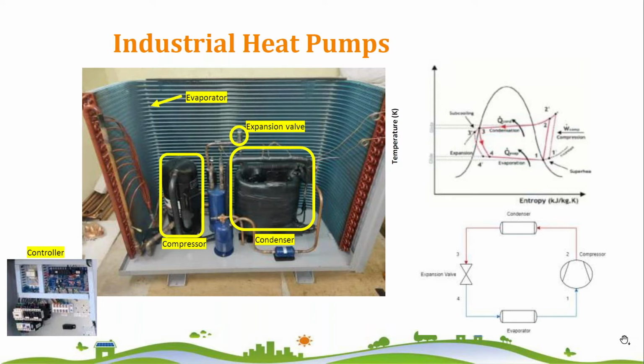Let's get into the working principle of the heat pump. There are 4 main components in the heat pump system: compressor, condenser, evaporator, and expansion valve. Initially, low boiling refrigerant inside the evaporator takes heat from the ambient air or the waste heat from industrial processes and gets boiled. This superheated vapor goes to the compressor where it is converted to high pressure and high temperature superheated vapor, which is then fed into the condenser, where the refrigerant condenses to a subcooled liquid by giving off heat to the process fluid going through the heat exchanger. This subcooled liquid is then fed into the expansion valve where it is depressurized to a mixed phase of gas and liquid. This mixed phase comes back to the evaporator. This cycle continues until the process temperature requirement is met.